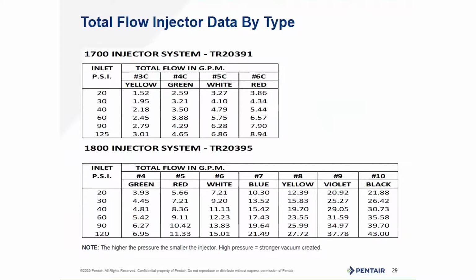So that's a situation where they don't have the injector balanced to the resin in the tank. So it's really about getting that information right. And essentially, they're dropping the percentage of brine low, and they're not going to get full regeneration on the resin, and they probably have short life on the resin in those circumstances, because you're probably brining well below that 10% solution.